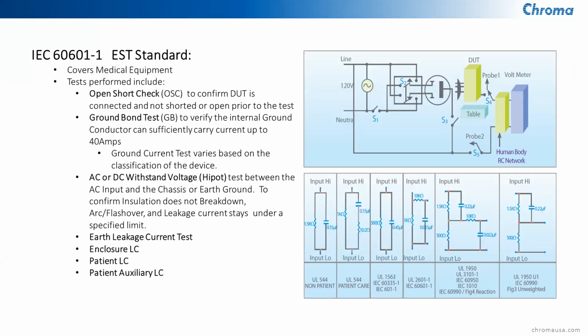And then, of course, the most stringent one would be the medical industry, which is the IEC 60601-1. This one does get into some additional leakage current test requirements, such as the enclosure leakage current test, patient and patient auxiliary testing. And here I've shown just a quick view of the various different types of impedance networks that would be used to simulate various human body networks or impedances. And they do vary, as you can see, based on the standards.